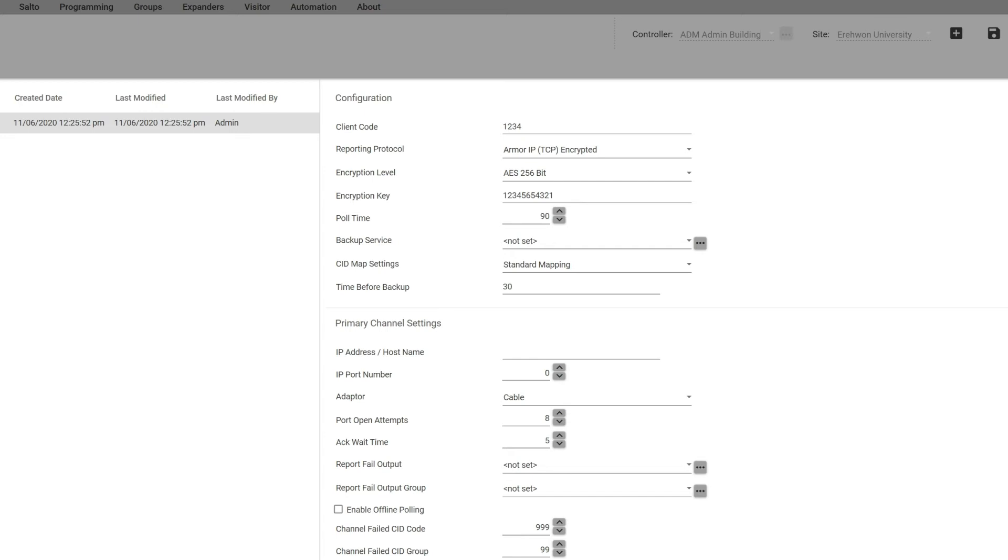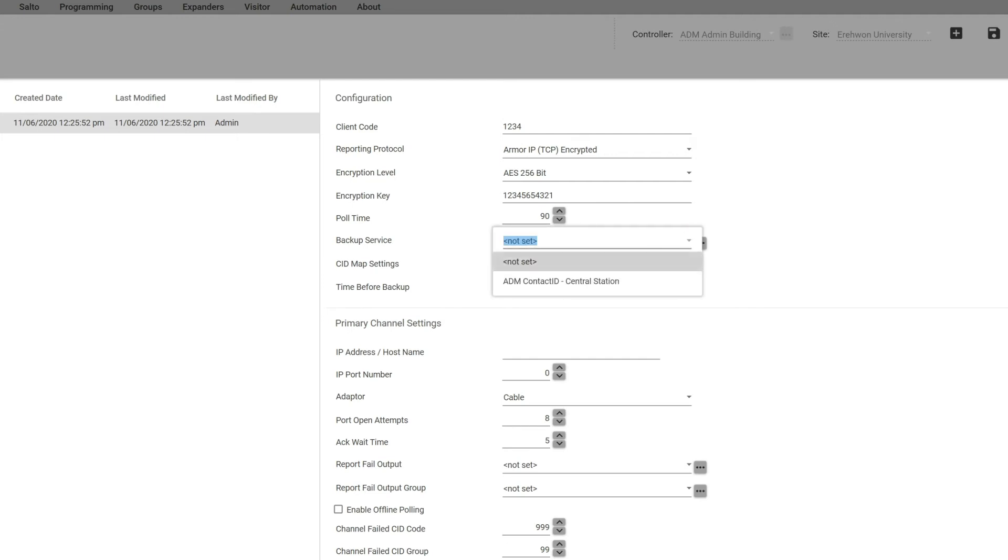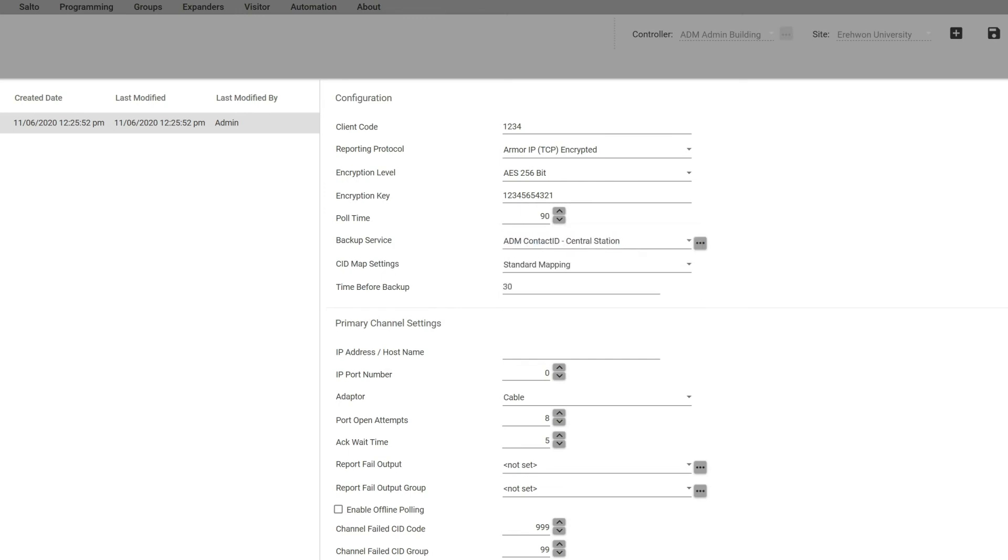The poll time you want to change probably to 90 seconds, that's the standard time to call out to the station and make sure that messages are being received on both ends. If after you attempted a certain amount of times, for example in this case maybe eight times, it's going to then tell you hey this isn't communicating and it might then go to your backup service, which in this case I would recommend you do have two services, one being Armor IP and if you do have the telephone lines already there then you might as well use it for Contact ID as your secondary.